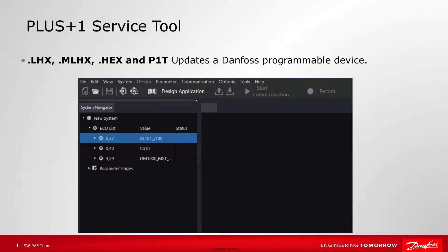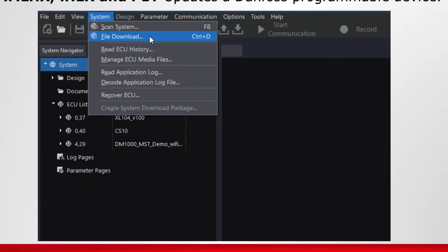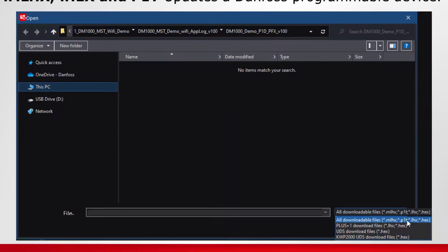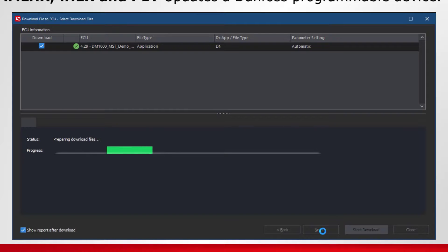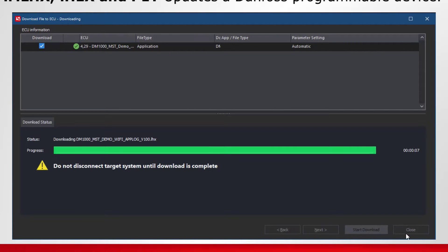When you have connected to your Danfoss device, you will see it in the ECU list in the left panel of the service tool. Often times you will have been given a file to read or write parameters or update a controller. Some of the more common files are LHX, MLHX, HEX, and P1T files, which are used to update a controller. This can be done by clicking on System in the top menu, then File Download. In the file browser, select your file and the file type, then step through the download wizard. It will automatically detect if there is an ECU it can download to. Most downloads do not take more than a couple of minutes, but this will depend on the amount of changes in the update and the speed of the connection.